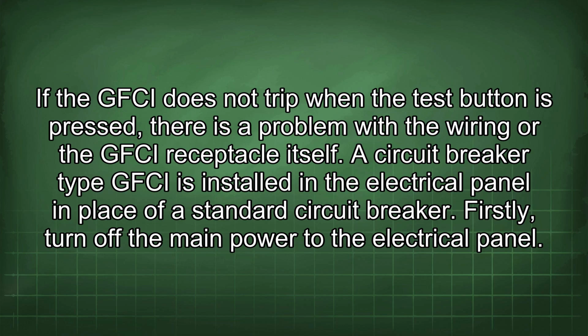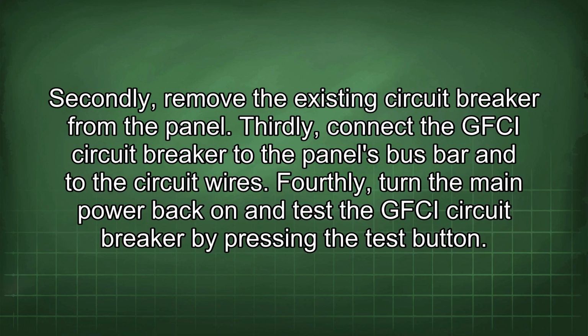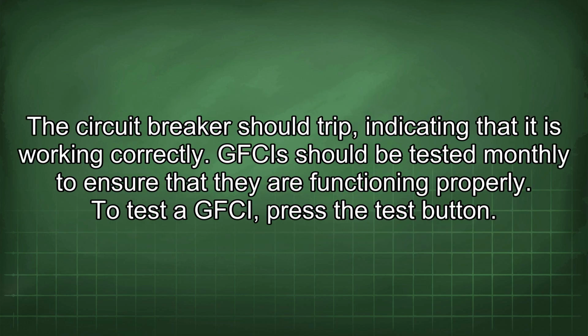A circuit breaker type GFCI is installed in the electrical panel in place of a standard circuit breaker. Firstly, turn off the main power to the electrical panel. Secondly, remove the existing circuit breaker from the panel. Thirdly, connect the GFCI circuit breaker to the panel's bus bar and the circuit wires. Fourthly, turn the main power back on and test the GFCI circuit breaker by pressing the test button. The circuit breaker should trip, indicating that it is working correctly.